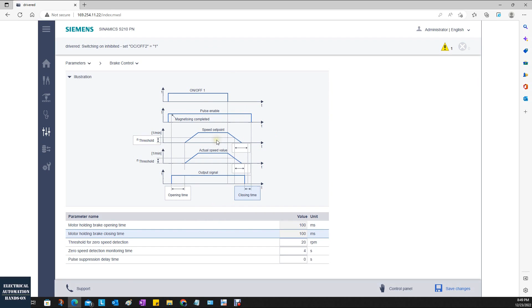In some cases you will see the relay or the brake burn out very soon. That's because this threshold of 20 RPM may be too high. Sometimes the motor, with high inertia, is still spinning, and then you turn on the brake. That causes the brake at the end of the motor to burn out very soon. Okay, you need to monitor this according to your application. Okay, this is the brake. This diagram is very useful.